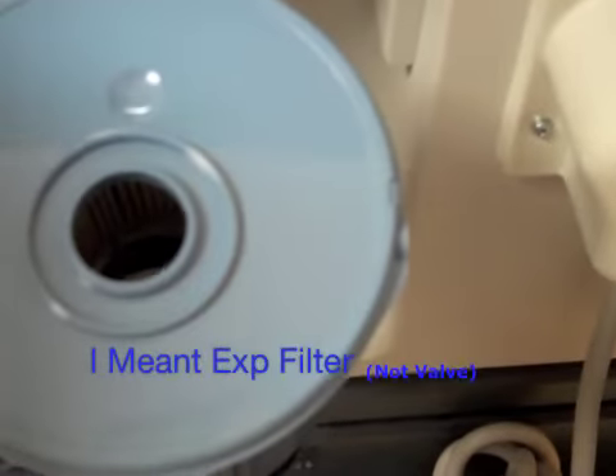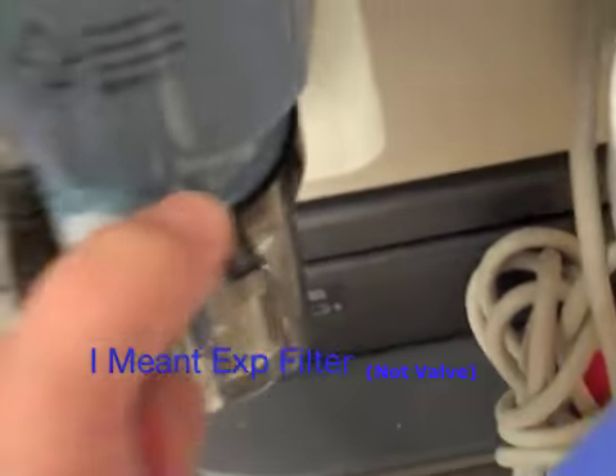Blue line with heater wire all the way through it going down to my patient Y. It's got a temperature measurement at the chamber, and a temperature probe also just before the patient Y. Exhalation is also heated going into my expiratory assembly. This is my expiratory valve with my water trap. Push that in, and you're going to slide that bar down to lock that in.